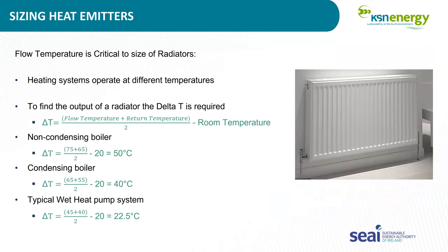The next thing then, how do you calculate the delta T? So the formula is there. Basically it's the flow plus the return temperature, averaged, so it's the average temperature of the radiator less the room temperature. And that will give you what's known as the delta T. That's another way the manufacturers describe the output of a radiator. They might give flow and return temperature, or they might give delta T.